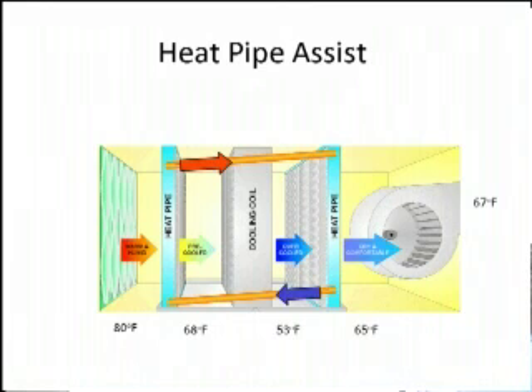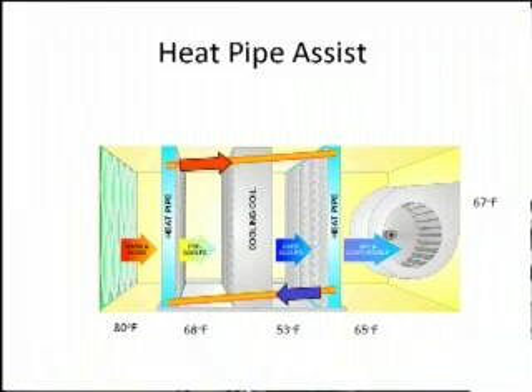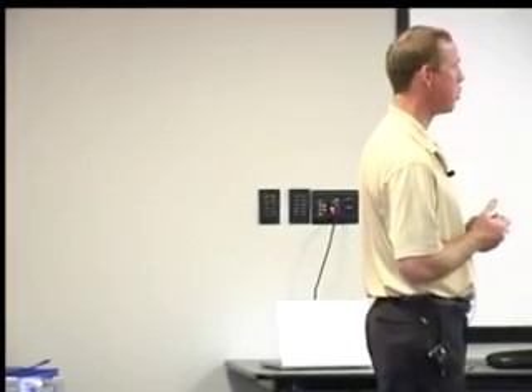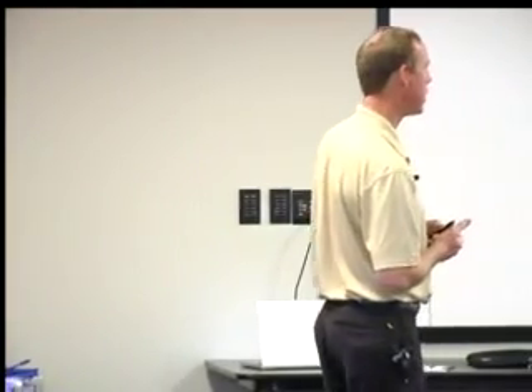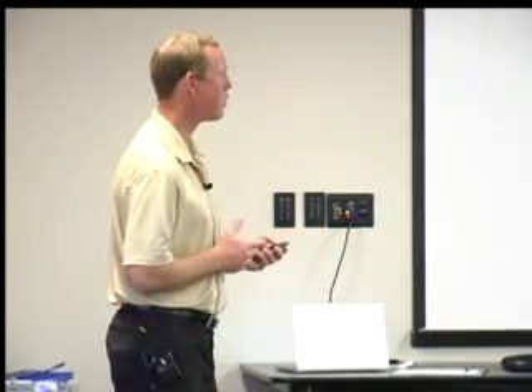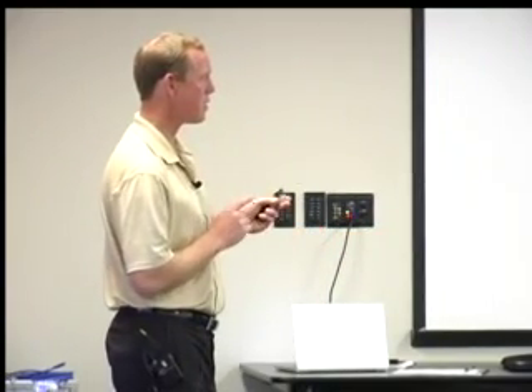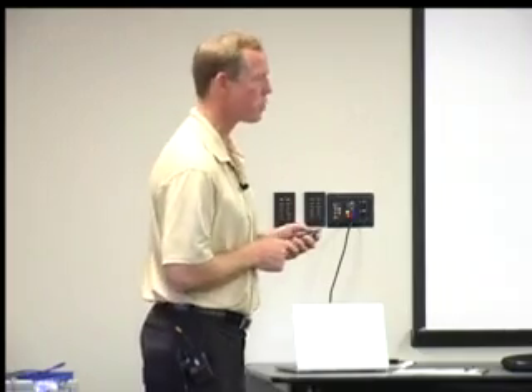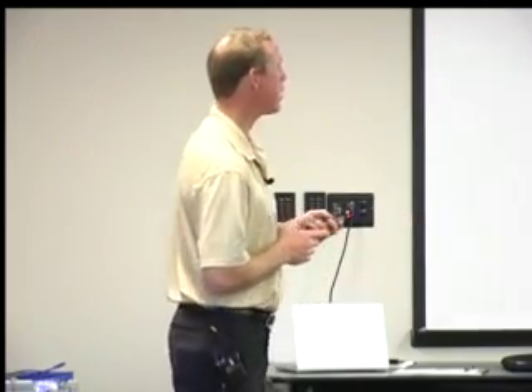Then we're reheating that air in a dry way — we're not adding any moisture to it. So it's purely sensible heating, just like an electric heat strip would do, to get it back up to 65 degrees to go into the space. That's actually a really good supply air temperature for a lot of spaces that wouldn't require any additional heating. So that's a very efficient approach, and this is actually easier to retrofit than the last one, so I'd encourage you to look at it. There are a bunch of manufacturers out there that make this technology.